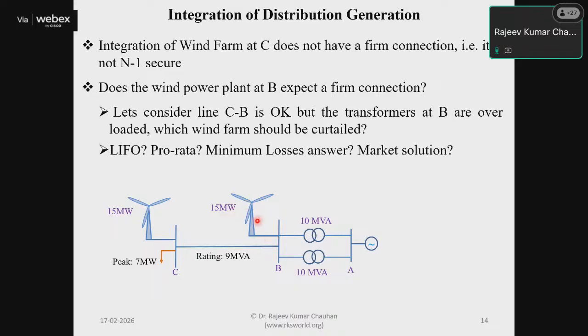So here we have 15 megawatt, then 9 megawatt, and around 8 megawatt will be here, or 7 megawatt if we consider a 0.8 power factor. Then 7 plus 15 is 22 here, but the rating of the transformers is only 20, so these transformers may be overloaded if we are feeding back, and then management is required. Let's consider line CB is okay. In this case we may have surplus generation here, but the 7 is there, so this line is able to carry the power generated by this power plant to the grid. But this area may be a problem because the maximum capacity of power exchange is only 20 MVA.